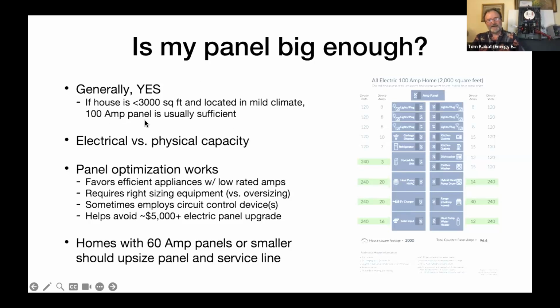And we find, you just have to try harder up to 3,000 square feet to fit it on a 100 amp panel with car charging. And so it's doable. It's pretty easy. A lot of our panels are pretty underloaded as it is, but there's 2 issues. One is the electrical capacity for amps, or we can also talk about watts, which are proportional to amps, or the physical capacity to fit the breakers in. But both problems are solvable.